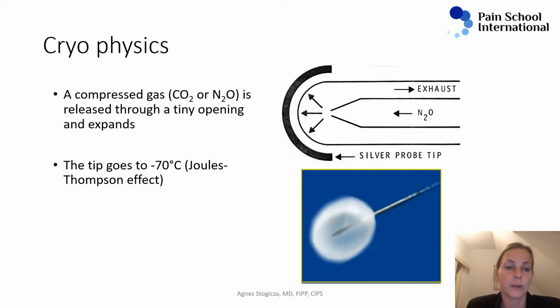What is the physics? The physics is based on the Joule-Thomson effect. So there is compressed gas, nitrous oxide or carbon dioxide, that comes very, very compressed, and as it comes out at the tip, it expands and cools down the tip. And then the gas leaves in an outer tube.